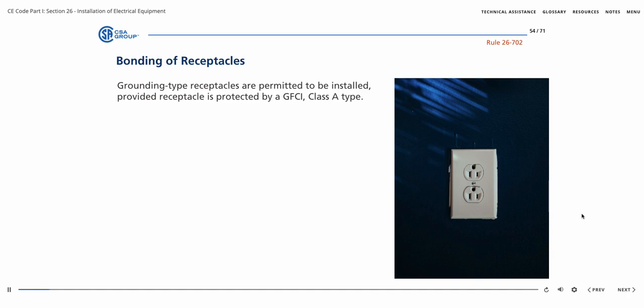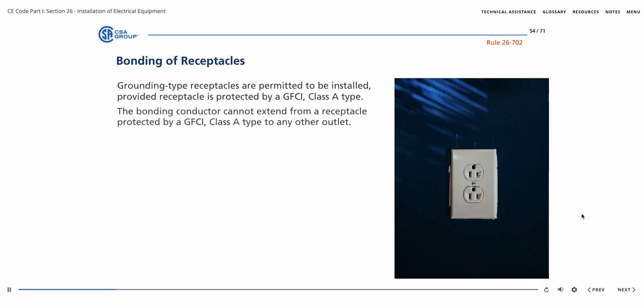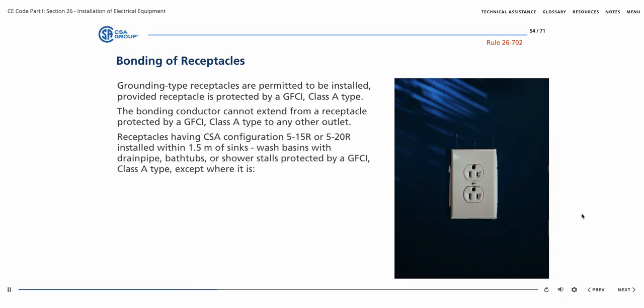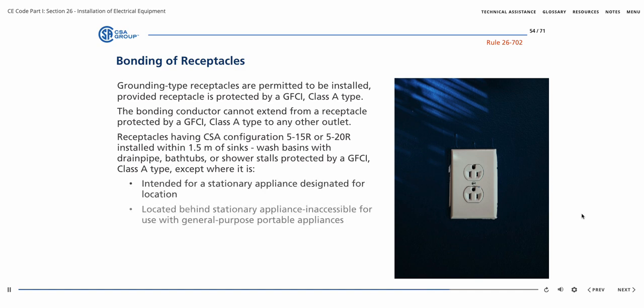Grounding-type receptacles are permitted to be installed, provided the receptacle is protected by a GFCI Class A type. The bonding conductor cannot extend from a receptacle that is protected by a GFCI Class A type to any other outlet. Receptacles having CSA configuration 5-15R or 5-20R installed within 1.5 meters of sinks, wash basins with drain pipe, bathtubs, or shower stalls are to be protected by a GFCI Class A type, except where the receptacle is intended for a stationary appliance designated for the location and located behind the stationary appliance, inaccessible for use with general-purpose portable appliances.